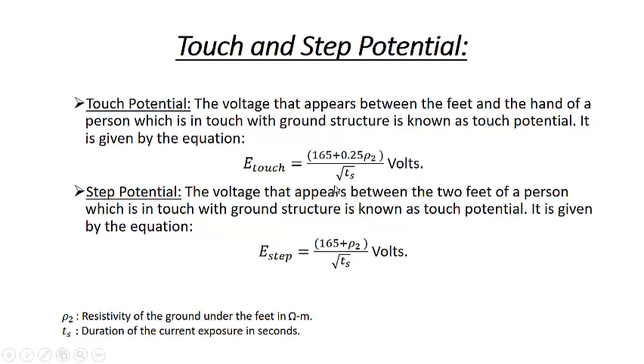Usually this Ts is not in our hand, it depends upon the relay structure. We have to decrease this rho 2, that is the resistivity of the ground structure. In case of substations, we make the ground mats or ground mesh in such a way as to reduce the value of this rho 2, because in case of earth fault, when the fault occurs involving the earth, the fault current will flow through the earth, that means the ground structure, and when the current flows through the ground structure, that current multiplied by the resistance of the ground structure will give some potential, and when that potential appears across our legs or between our hand and the feet, some voltage will appear, and that we have just discussed, that is known as touch potential and step potential.